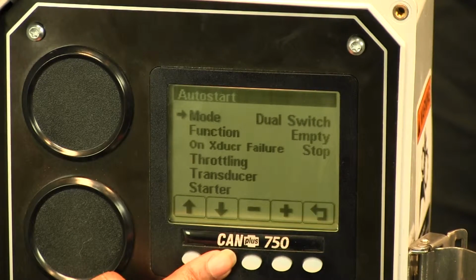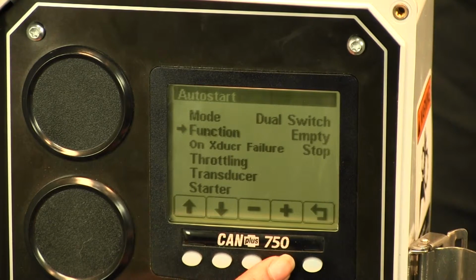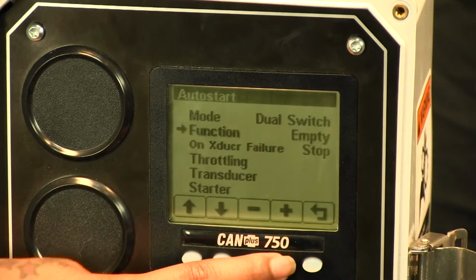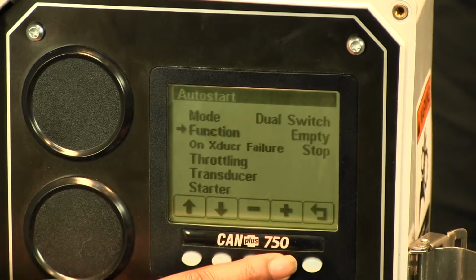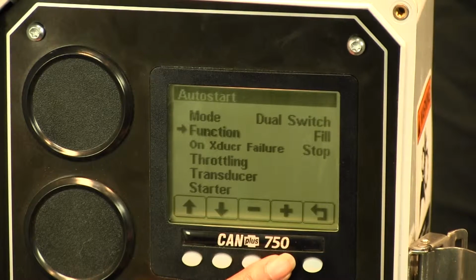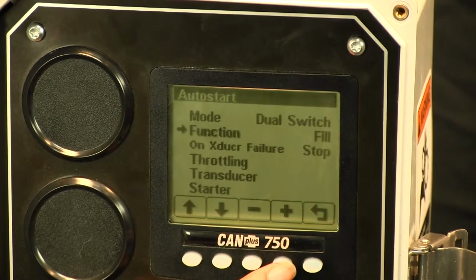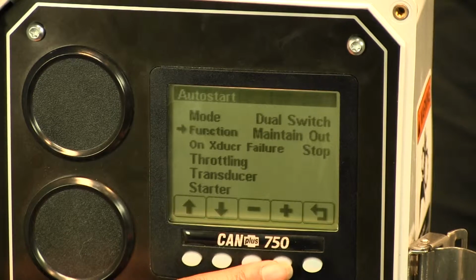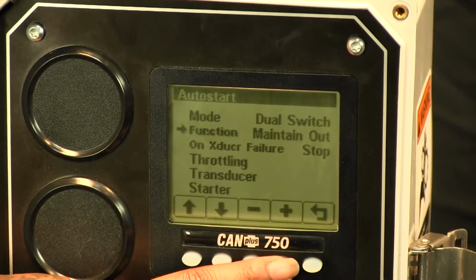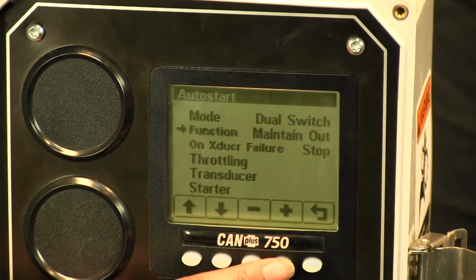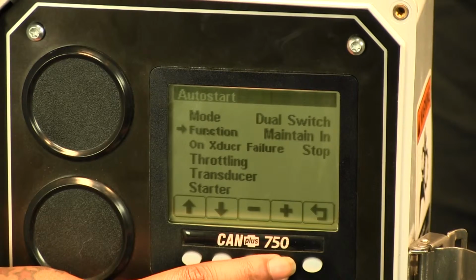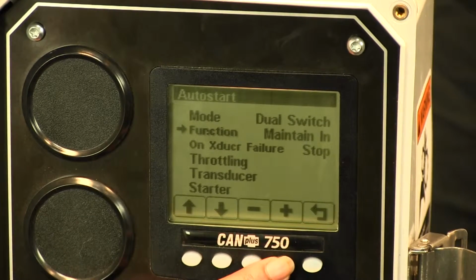Now with that, you have the different functions available, and there's empty, which you would use for when you want to get a level below a specific target. And then you have fill when you want to get a level or pressure above a specific target. Then you have maintain out, and that would be used when you're trying to maintain a level or pressure at or below a specific target. And then you have maintain in, which would be used if you're trying to maintain a level at or above a target.